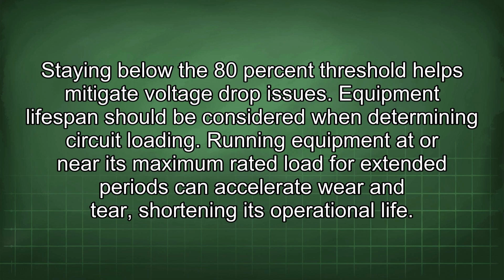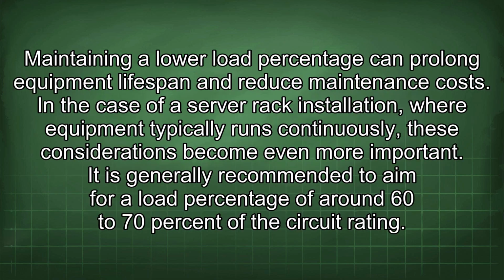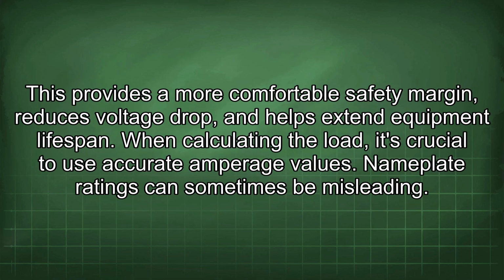Equipment lifespan should be considered when determining circuit loading. Running equipment at or near its maximum rated load for extended periods can accelerate wear and tear, shortening its operational life. Maintaining a lower load percentage can prolong equipment lifespan and reduce maintenance costs. In the case of a server rack installation, where equipment typically runs continuously, these considerations become even more important. It is generally recommended to aim for a load percentage of around 60 to 70% of the circuit rating. This provides a more comfortable safety margin, reduces voltage drop, and helps extend equipment lifespan.